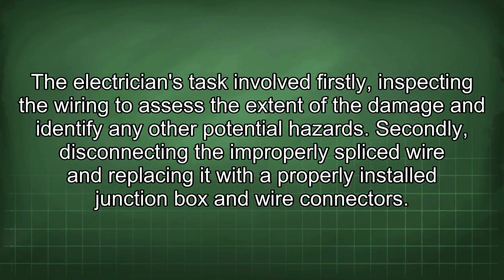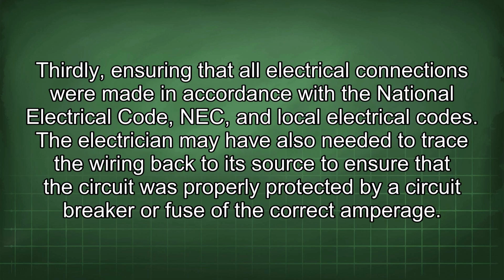The electrician's task involved firstly inspecting the wiring to assess the extent of the damage and identify any other potential hazards. Secondly, disconnecting the improperly spliced wire and replacing it with a properly installed junction box and wire connectors. Thirdly, ensuring that all electrical connections were made in accordance with the National Electrical Code, NEC, and local electrical codes. The electrician may have also needed to trace the wiring back to its source to ensure that the circuit was properly protected by a circuit breaker or fuse of the correct amperage.